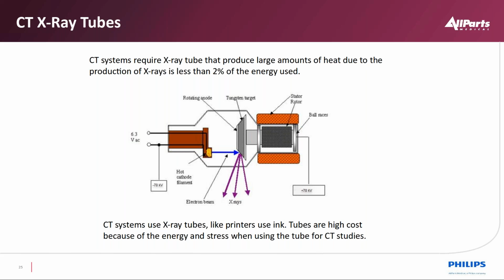We use a lot of energy, and with regards to that energy, there is so much energy placed here. We have to make sure that during PMs, fans are working and all the heat exchanger filters are clean. So we're moving a lot of heat. The gantry room gets really warm. There are a lot of fans in there to manage temperature. One of the highest expenses on a CT scanner is the X-ray tube. On some machines, we've seen this tube cost $250,000. So we need to be good at qualifying that we have a bad X-ray tube.